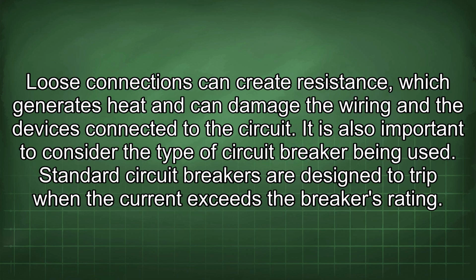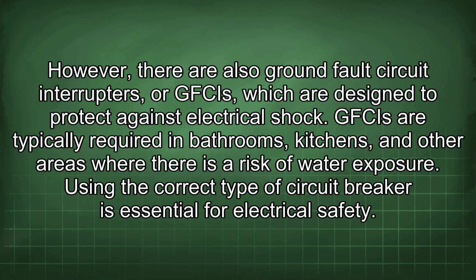It is also important to consider the type of circuit breaker being used. Standard circuit breakers are designed to trip when the current exceeds the breaker's rating. However, there are also ground fault circuit interrupters, or GFCIs, which are designed to protect against electrical shock. GFCIs are typically required in bathrooms, kitchens, and other areas where there is a risk of water exposure. Using the correct type of circuit breaker is essential for electrical safety.